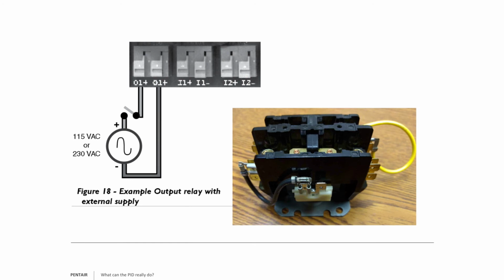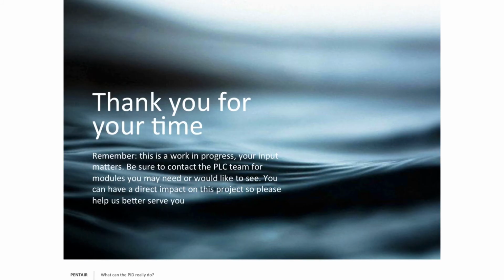By doing this, remember, this is the way to do it. We take that inductive load off of our circuit and put it on the mag relay or the pump relay, which is rated for the horsepower and amp draw of the pump proper, so we don't damage our unit. Now I know that was kind of quick, a little bit of it. Here's a few answers to remember.